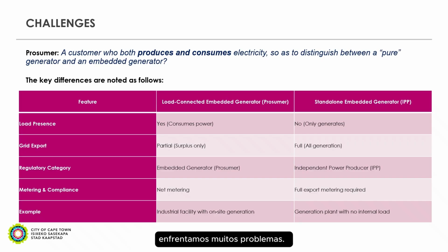And with that, we do get lots of issues where, in certain instances, a customer installs a 5 megawatt embedded generation plant and they have a notified maximum demand of 7 MVA and a load of around 6 to 7 MVA with the installed embedded generation of 5 MVA. They might not be exporting anything, unless over weekends with minimal load and maximum generation, but that will be only a couple of days within the year. And that is where there's a major difference between a prosumer who would not necessarily export a lot of capacity as opposed to an IPP whose full generation is being exported onto the network.